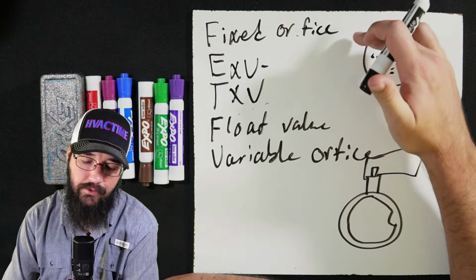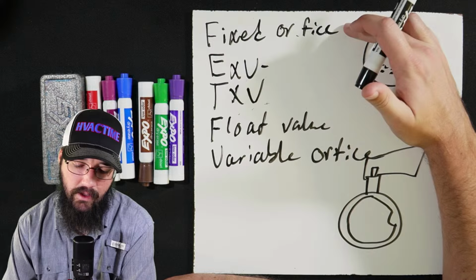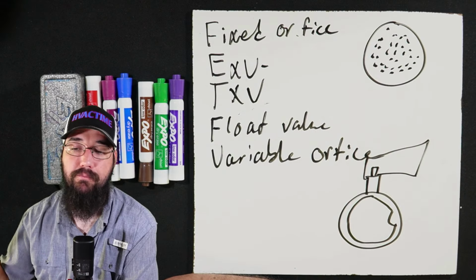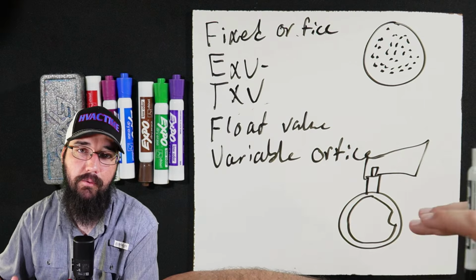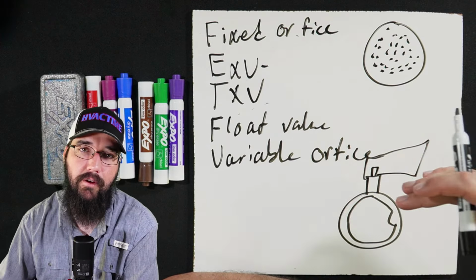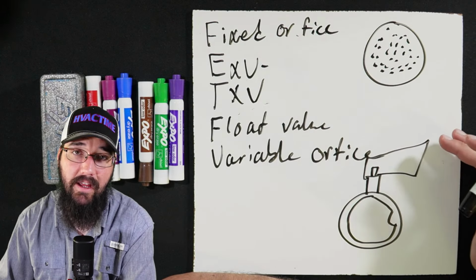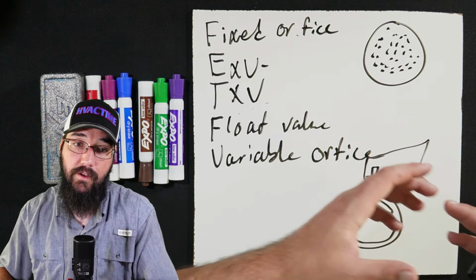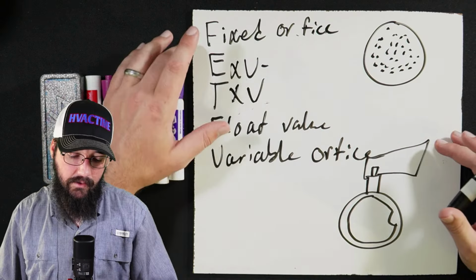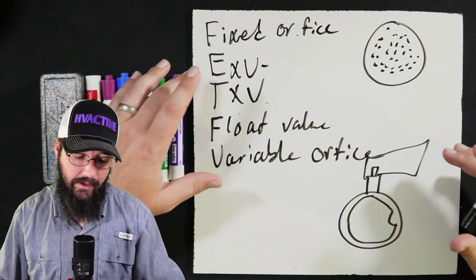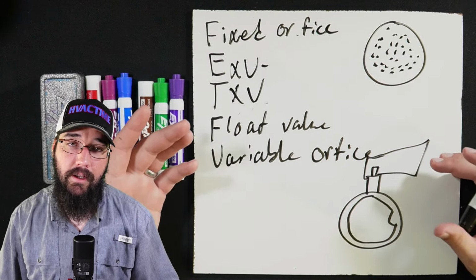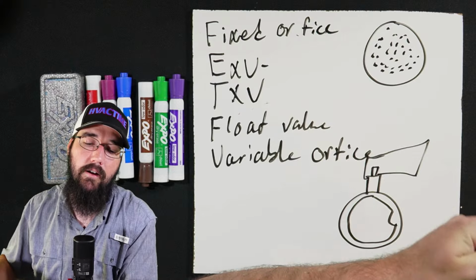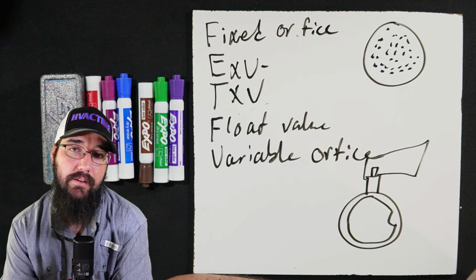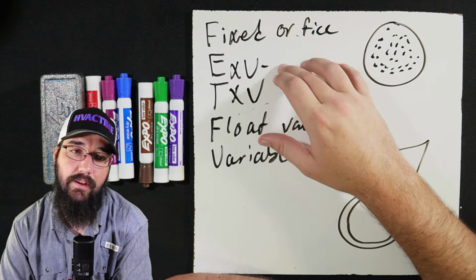So with these styles of metering valves, or metering devices, these can scale all the way up to machines that are doing thousands of tons, 3, 4, 5,000 ton machines. These valves are capable of scaling to those sizes because this variable orifice just makes the orifice bigger in the end. Where with the EXV, at some point, we end up with these just really gigantic valves that just don't fit. And they'd be so expensive and hard to work on, they just don't make sense. And so by the time you get to those sizes of machines, you just don't see this being used.